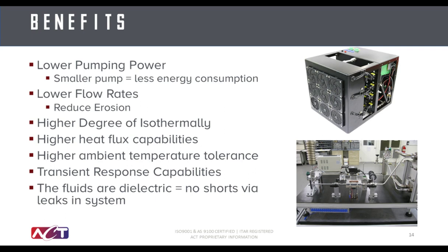The higher heat flux capability of pump two-phase we've addressed is also an issue when trying to achieve this with single-phase cooling. And also the higher efficiency of a pump two-phase system allows for higher ambient temperatures or higher cooling medium temperatures. This is a particular benefit for data center cooling applications where you want to reduce the load on your chiller and improve your energy efficiency. Also, the dielectric nature of most two-phase fluids is a major benefit for high voltage applications and applications where electrical isolation is important.